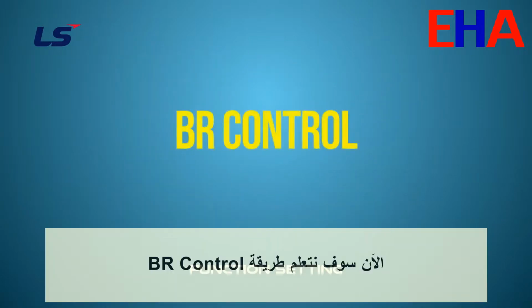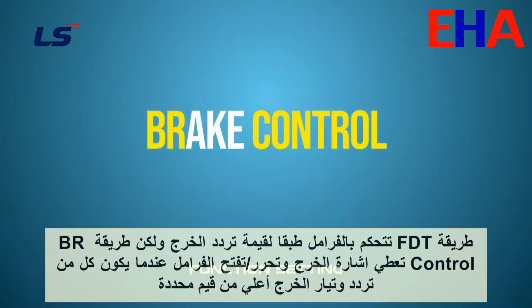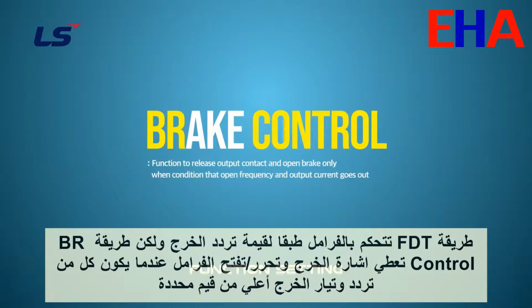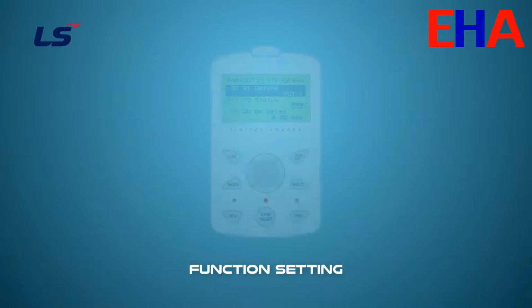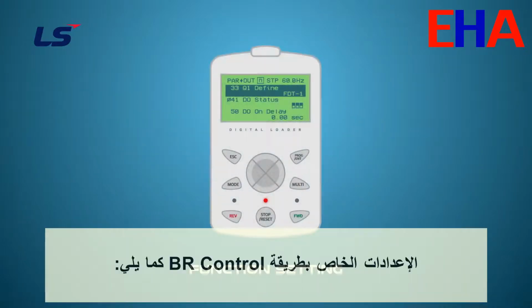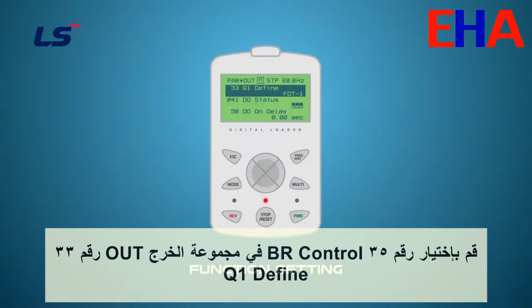Next, we will learn about the BR control functions. If the FDT has controlled the brakes according to the output frequency, the BR control function will only release the output and release the brakes if both the output frequency and output current are above the set value. Let's set the BR control function. Set 35 BR control for the output at outgroup 33 Q1 define.